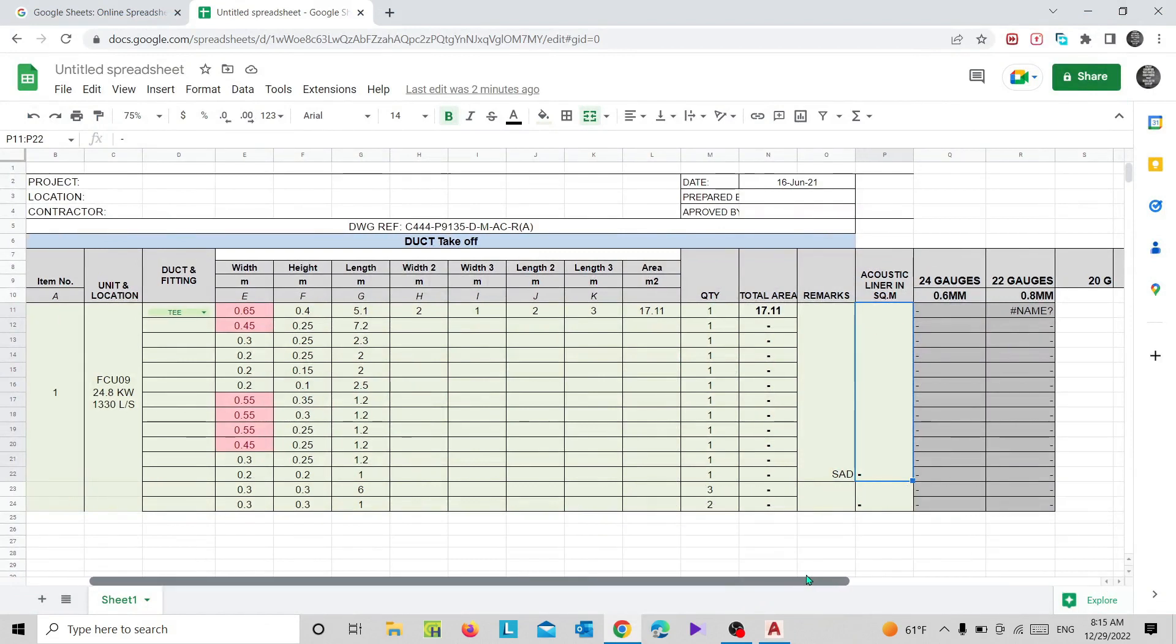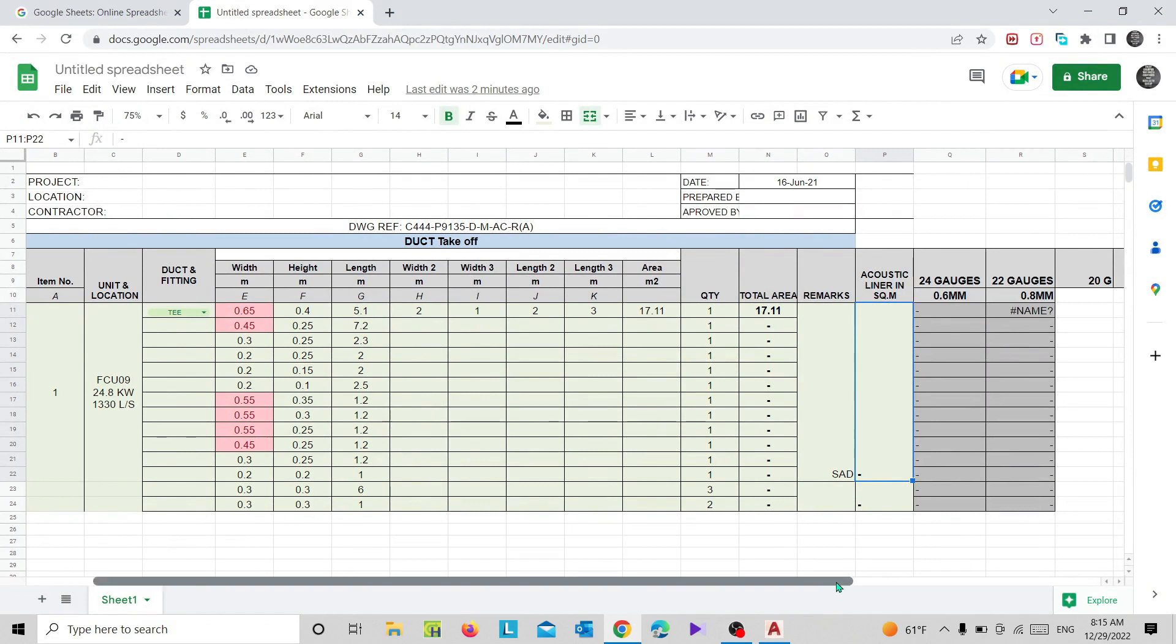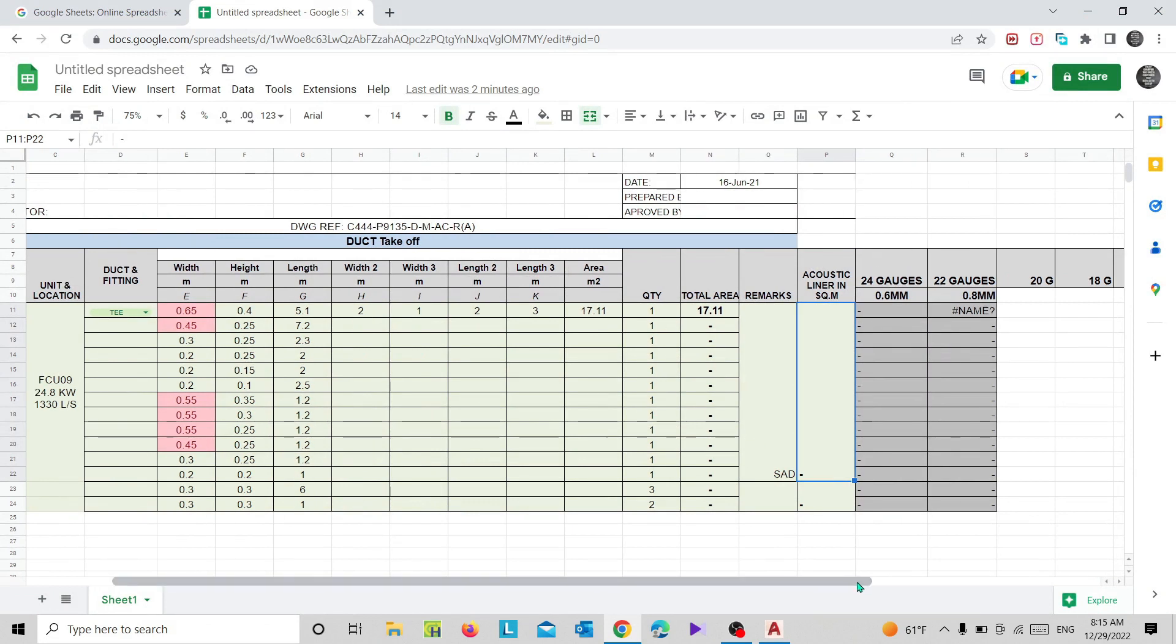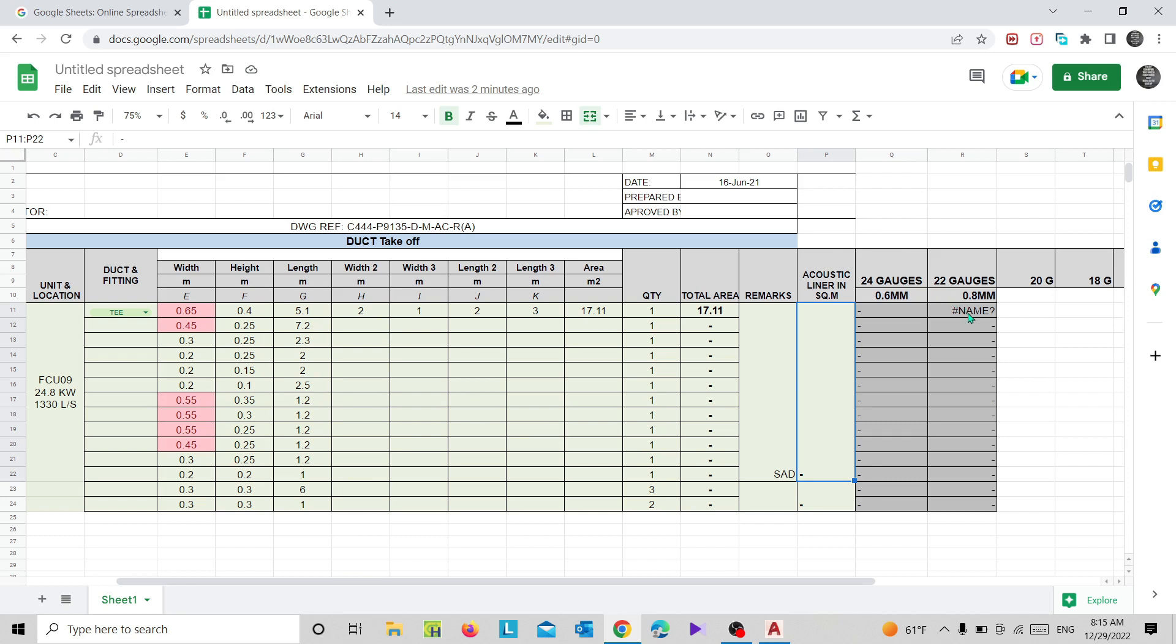Next one is gauges of the duct. We have 24 gauge duct, 22 gauge duct, 20 gauge duct, and 18 gauge duct. The gauges could be decided based on the standards that you are following - it could be from SMACNA or else DW 144. Depends on your standard, you can choose whatever the duct gauge you need by referring the standard.